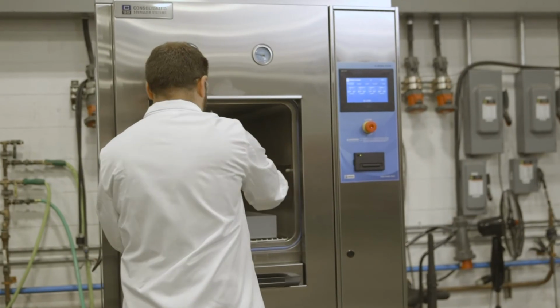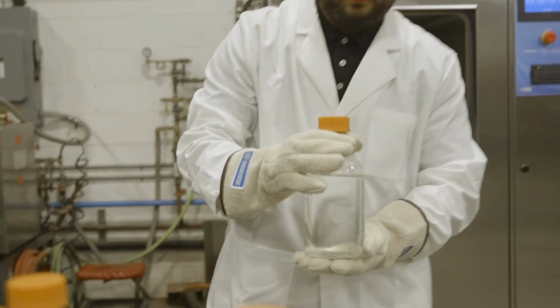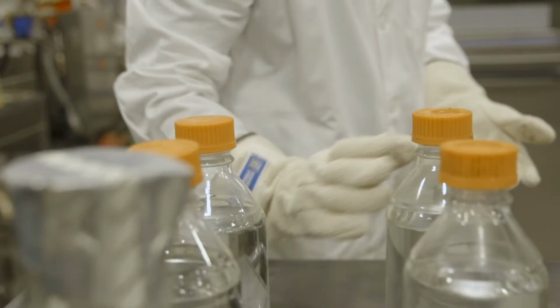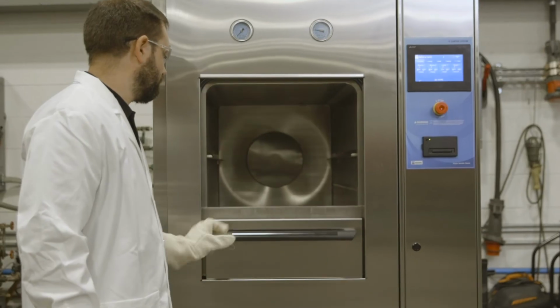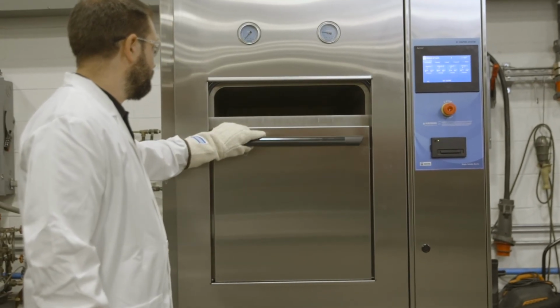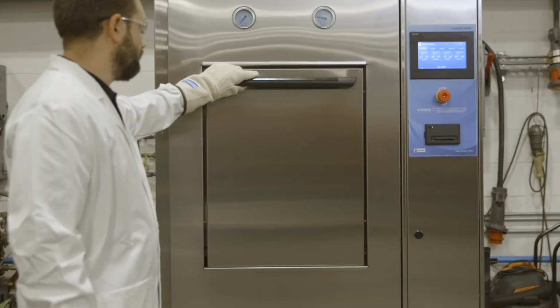Be careful not to agitate any liquid containers or remove caps while unloading, as this can lead to scalding or burning from boiling liquids. Place all goods in a clearly designated area and allow them to cool to room temperature. Close the autoclave door once complete. This will help save energy as many autoclaves have steam flowing in the jacket throughout the day.